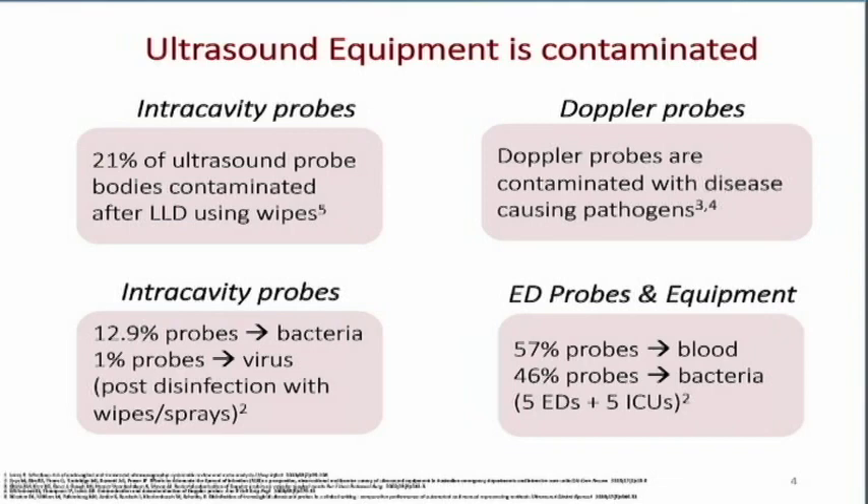In the ED, there's lots of action with trauma patients. 57% of those probes still had blood on them, and 46% of probes were contaminated with bacteria — found across five different emergency departments and five different intensive care units. It's very easy for our transducers to become contaminated, and more importantly, to pass those germs and viruses from patient to patient, as well as from patient to you.